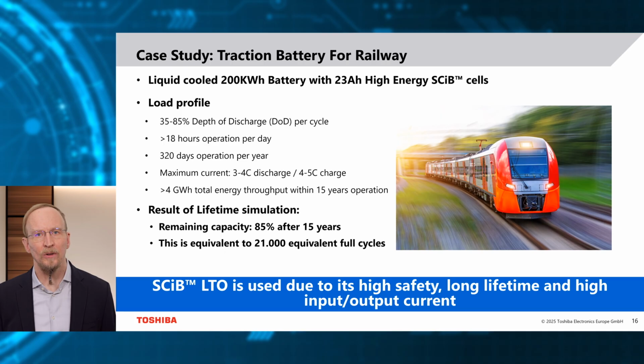The train is operated for over 18 hours per day and 320 days per year. The maximum current is around 3 to 4 C in discharge direction and around 4 to 5 C in charge direction. During the simulated operation of 15 years, the energy throughput amounts to over 4 gigawatt hours. The result of the lifetime simulation is that the remaining capacity after 15 years is still around 85%, which is equivalent to about 21,000 equivalent full cycles.